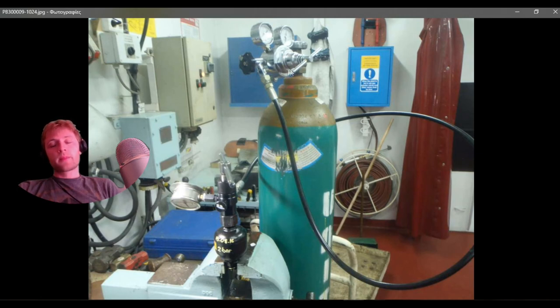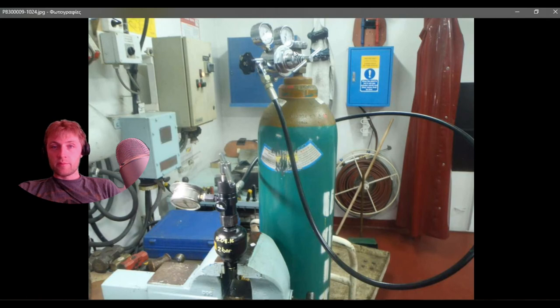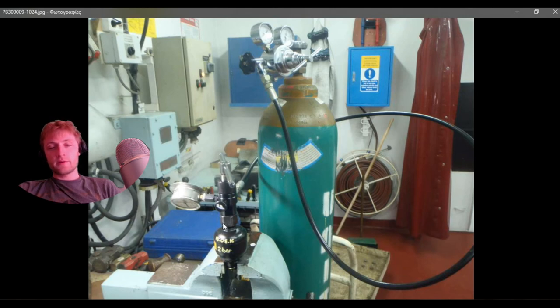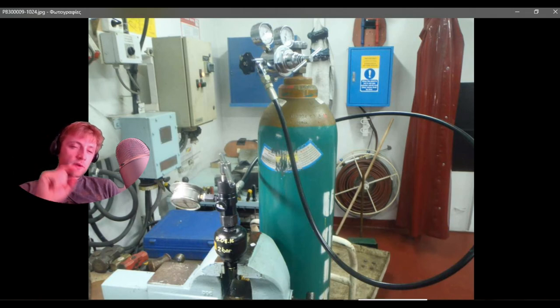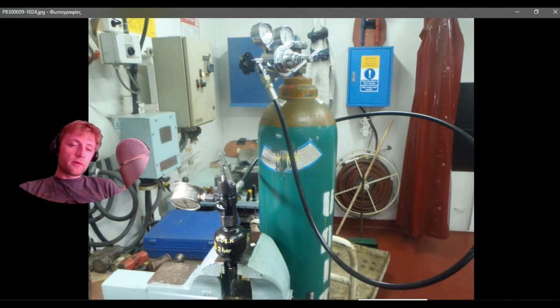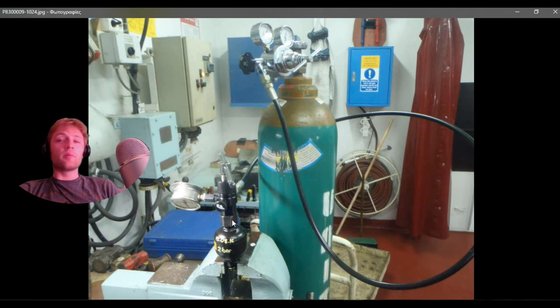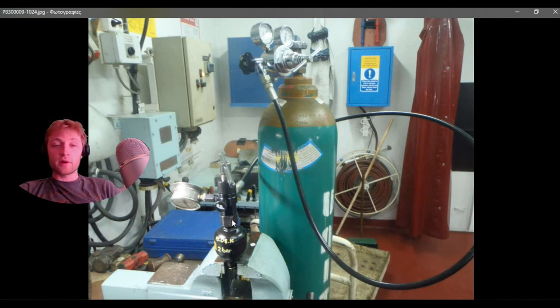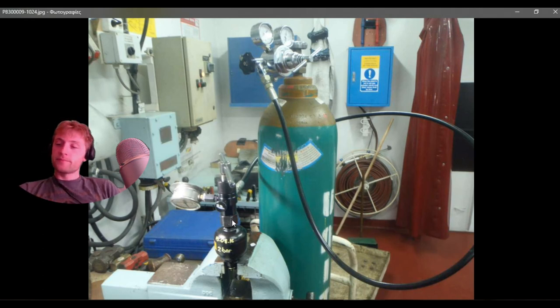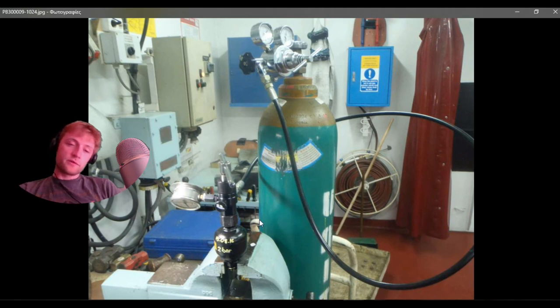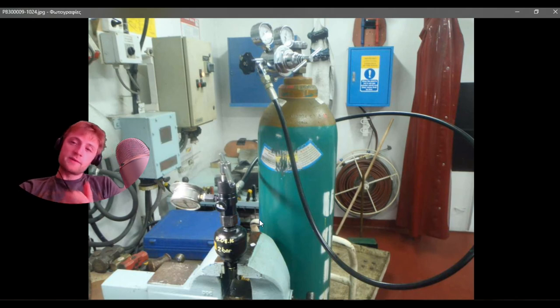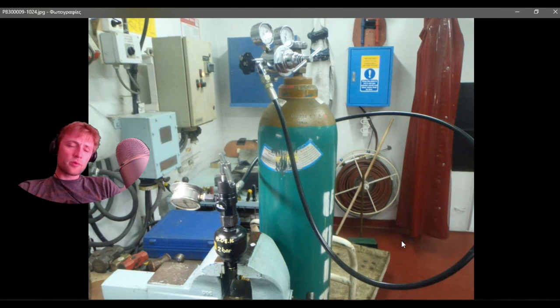Close this one, close also this one clockwise, and close the black one. When you are completely finished, you can close the main valve here, the gray one. Then you release this nut which is connected with the thread here. There is an O-ring below here. This plays a very important role because if you have any cracks on that O-ring, for sure you will have leakage from there. Be sure that you have these O-rings. This O-ring is very strong because when you tighten it, it is also pressed and needs to be checked.